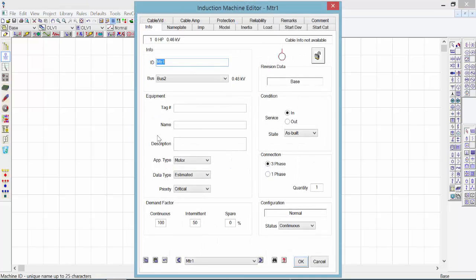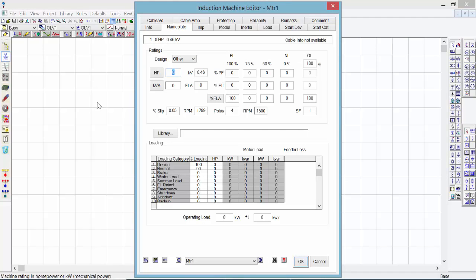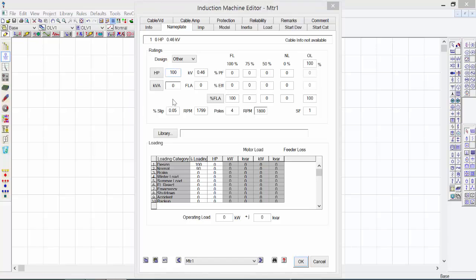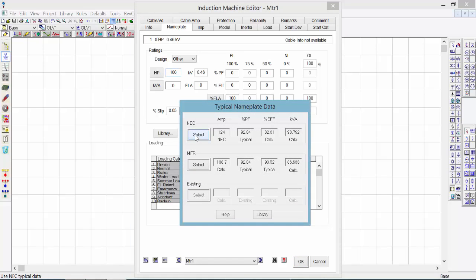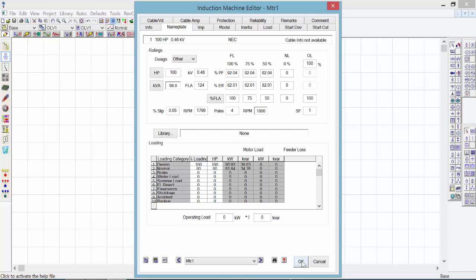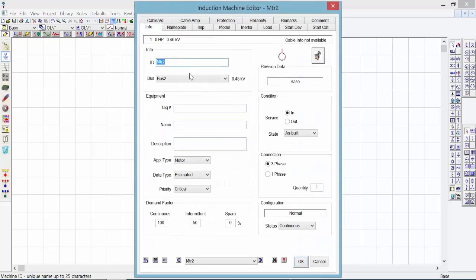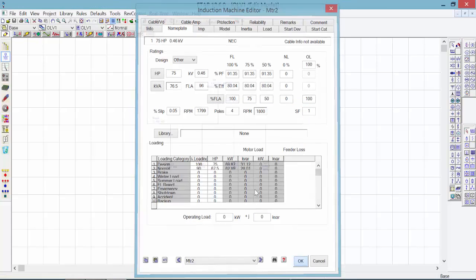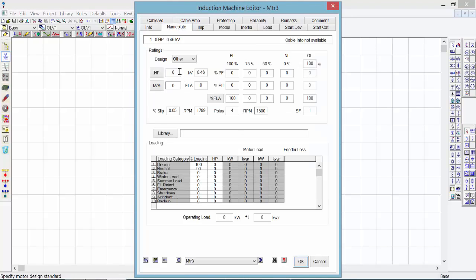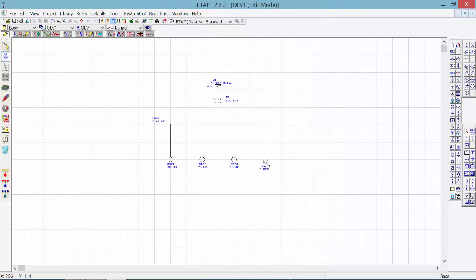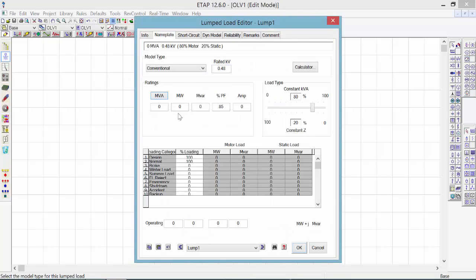Now for the motor number 1, let's go to the nameplate. Let's have this one the biggest one in terms of the horsepower and put 100 horsepower. And for the full load amp and other data for this motor, let's stick to NEC code. And click on OK. For the next motor, let's put 75 horsepower NEC and OK. Third one, let's put 50 horsepower, again NEC and OK. And for the lump load, let's put 25 kVA.